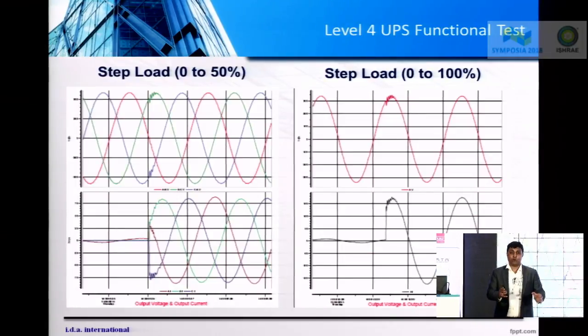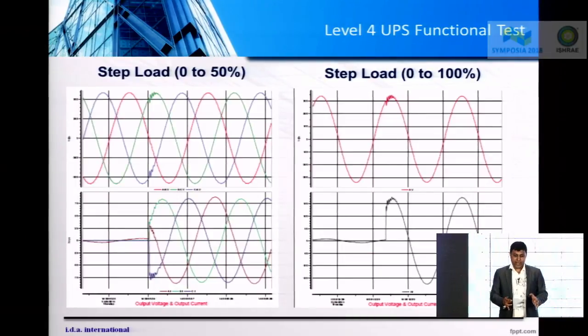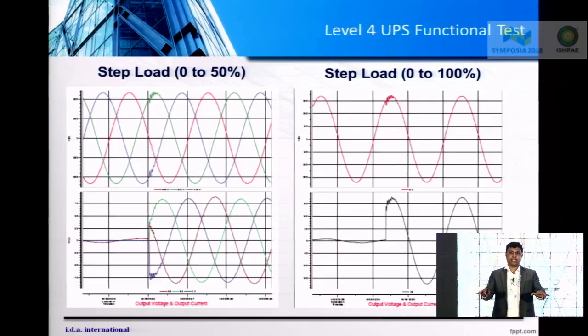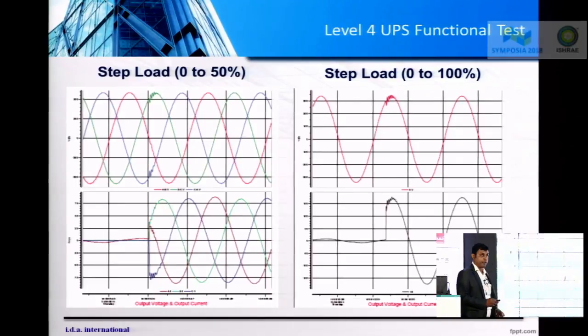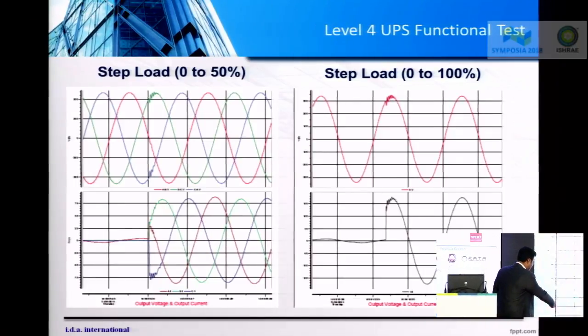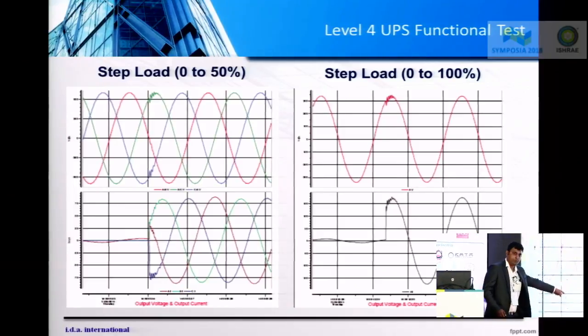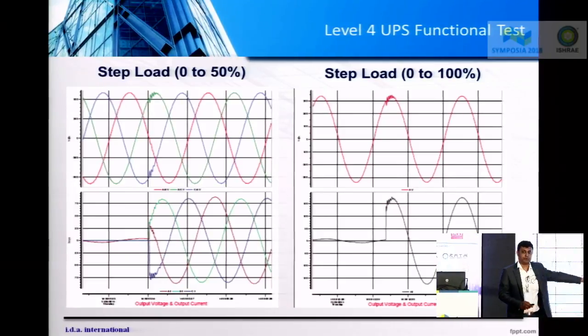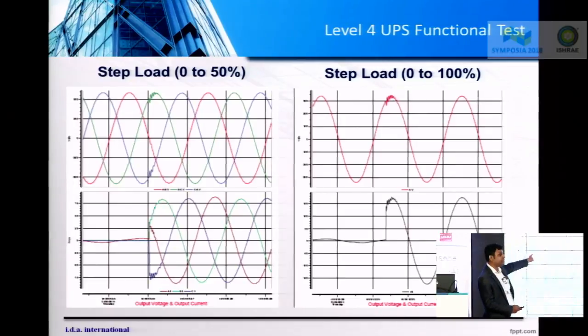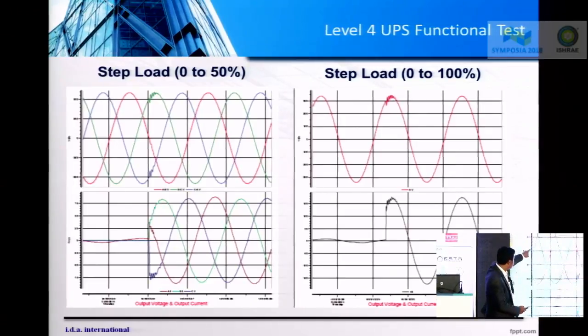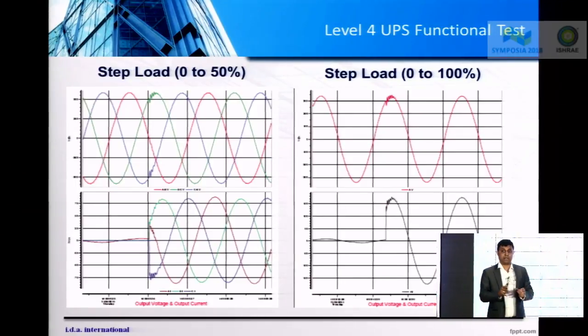Let's understand step load test or transient load test. When you have an equipment which is at zero loading condition and you suddenly put a load of 50% or 100% to a UPS, you can observe the following. You can see here the output current which is below. There was no load and suddenly you put 50% load. And then you have to observe the output voltage. You would see a small distortion at the output sinusoidal waveform. You have to ensure that the output voltage is not impacted.